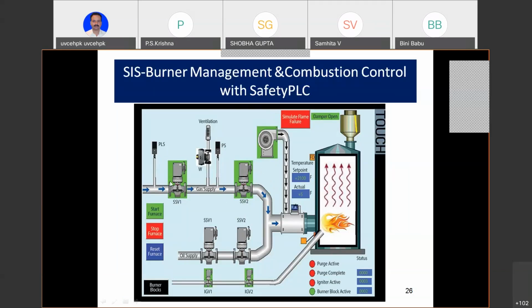This is what is known in safety instrument systems, a very popular term, called a block and bleed system. Now, in the block and bleed system, in the gas line, you don't want the gas to be trapped here. So what they do, particularly for gas, is this closes in an emergency, and this opens and goes to the ventilation. That means this pressure is depressurized by this system of 3 valves. This is another pressure switch, which shows the status of the pressure.